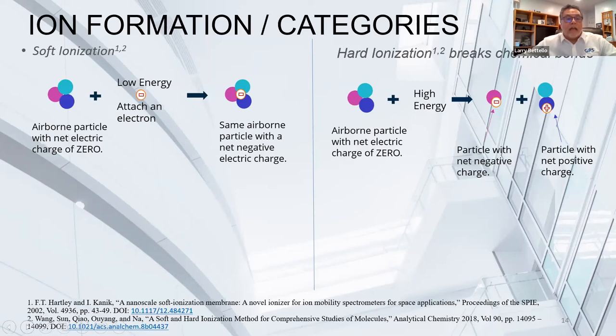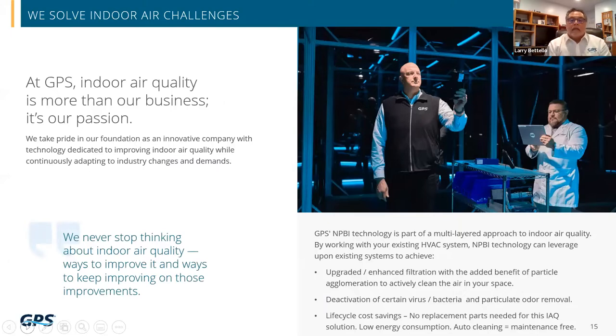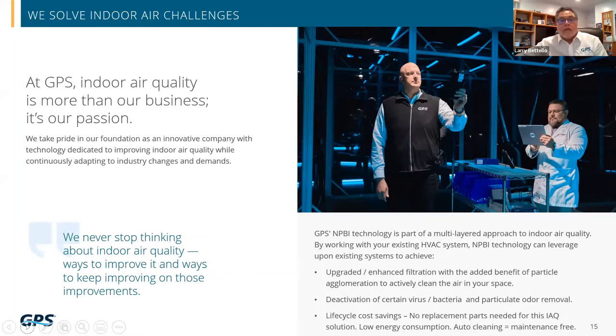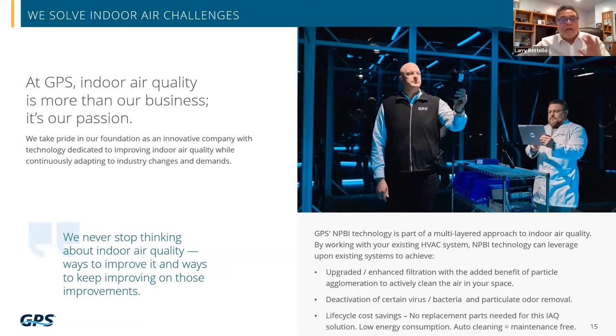In needlepoint bipolar ionization, opposites attract — positive particles are drawn to negative ones, they come together like magnets, and particles grow large enough to get caught in the airstream and captured by filters. GPS promotes a multi-layered approach to indoor air quality working with existing HVAC systems. The foundation must always be proper ventilation, adequate filtration, and air movement first. If you're not moving air and don't have filters, ionization alone is not appropriate.